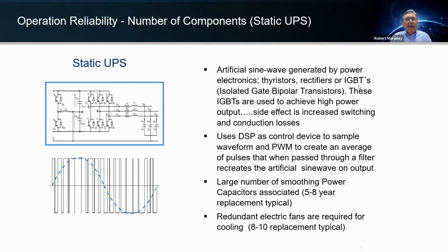So static UPS is traditionally artificial sine wave generated with power electronics: thyristors, rectifiers, IGBTs. As technology has progressed over the years, they've gotten better at it, more efficient at it, provided better technologies. They're using digital signal processing, DSP, in conjunction with PWM to create average pulses that they can use on the output. And then they use a lot of capacitors to smooth out that waveform so that it's acceptable to the downstream loads.